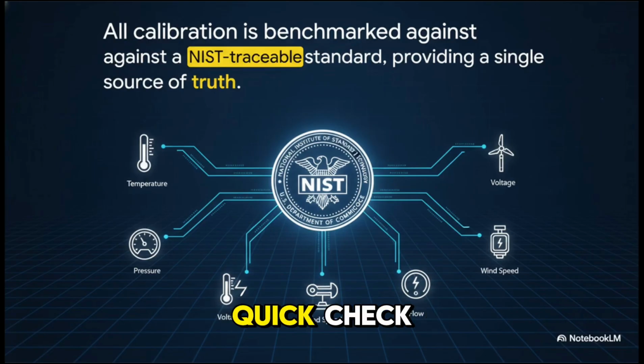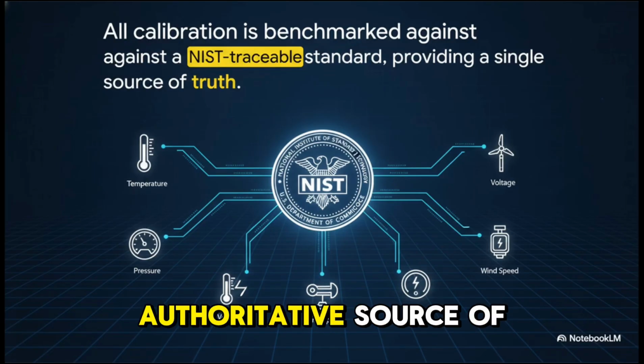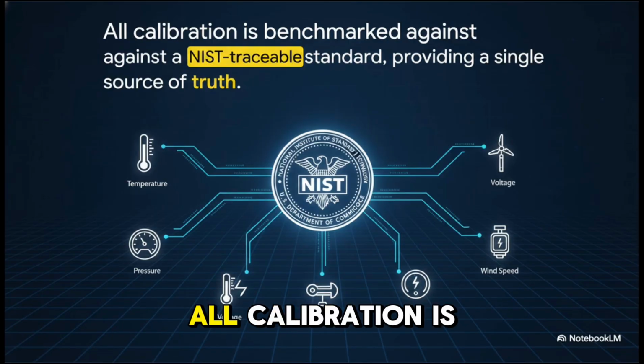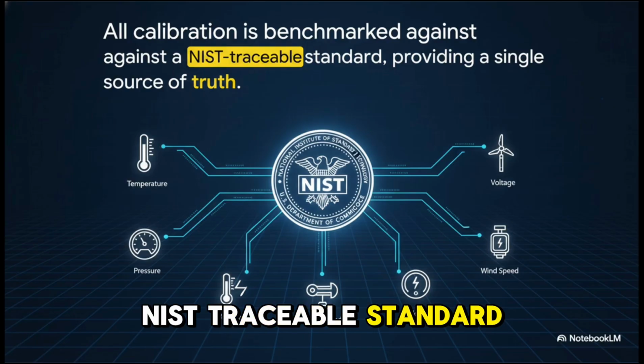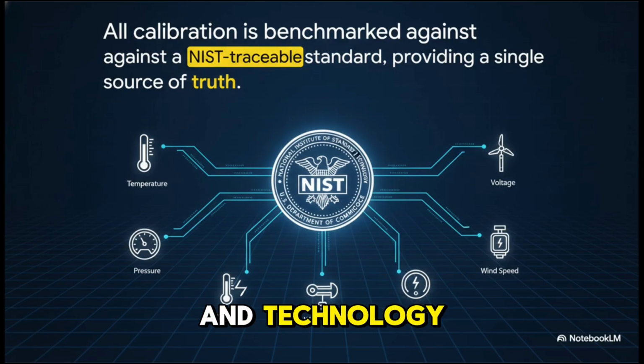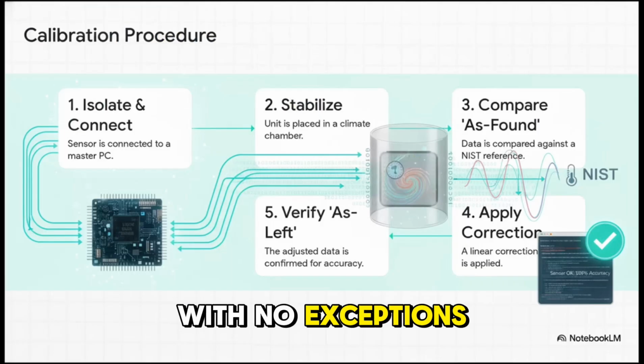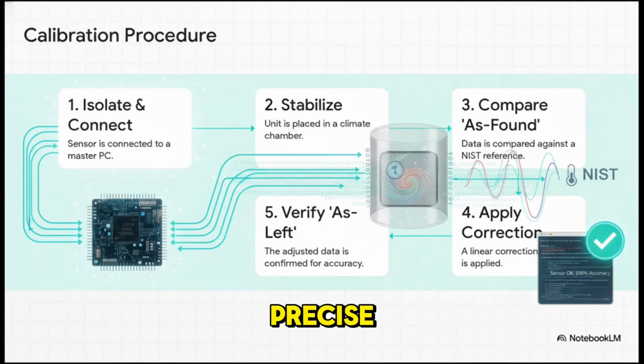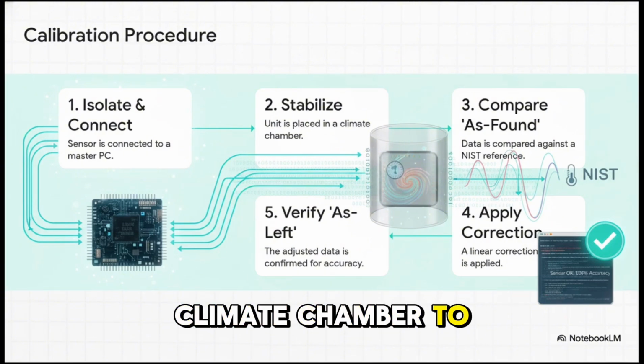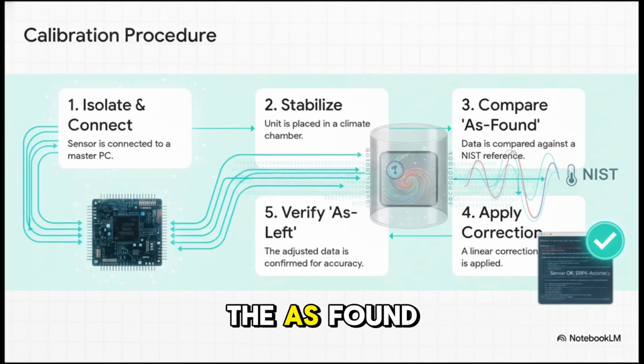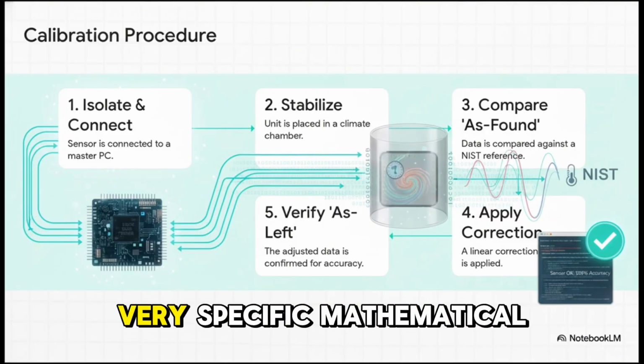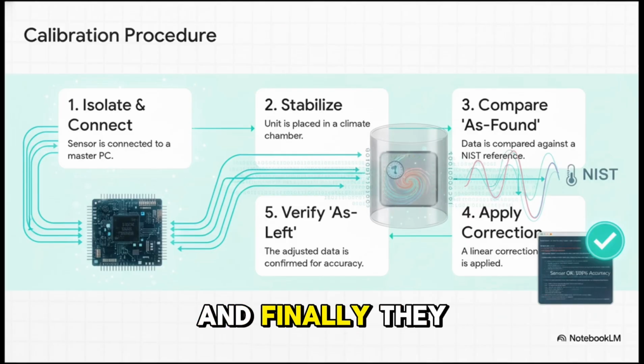And we're not just talking about a quick check. There has to be one single authoritative source of truth. For a sensor like this, all calibration is benchmarked against a NIST traceable standard. That's the National Institute of Standards and Technology. It's the ultimate ground truth that every single sensor has to be perfectly aligned with, no exceptions. The whole procedure is just incredibly precise. First, they take the sensor and hook it up to a master computer. Then it goes into a special climate chamber to stabilize. The technicians then take a reading, the as-found data, and compare it against that NIST reference. If it's off, even by a tiny bit, they apply a very specific mathematical correction in the software. And finally, they check it again to verify the as-left data, making sure it's now dead on.